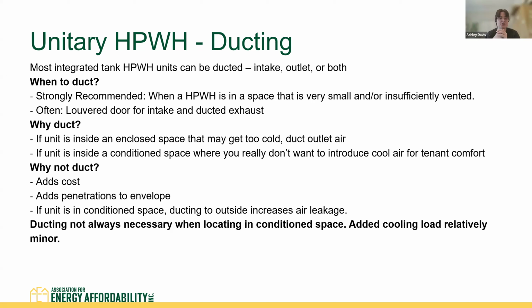Also, you might want to duct if you're inside a conditioned space where you don't want to just be dumping cold air on folks, especially if that water heater is located right in the room. Can be a little bit of a shock to walk past and get a blast of cold exhaust air. It's true that ducting does add cost, and it adds penetrations to the envelope, right? So if you're in a conditioned space, ducting to the outside can increase air leakage. It's not always required, the actual cooling load it adds is relatively minor. It's more about the comfort of just dumping it straight on people walking past. So there's some things to think about when you're thinking about the ventilation strategy that you're going to choose. Next slide.